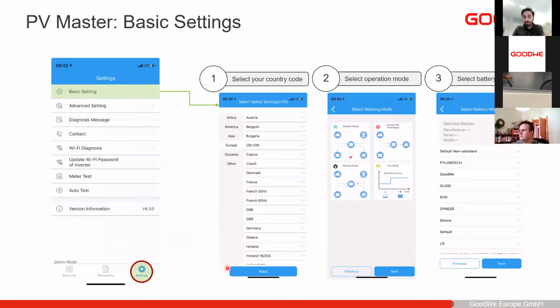So firstly, you need to select the country code or the safety code. This will configure the grid parameters of the inverter. Make sure here you have Africa, Europe, and so on. Make sure to try to find your country here. In case you do not find it, there are also some default settings under others. And here you have the default 50 and 60 hertz, for example. And then you can always, afterwards, configure the specific grid settings manually.